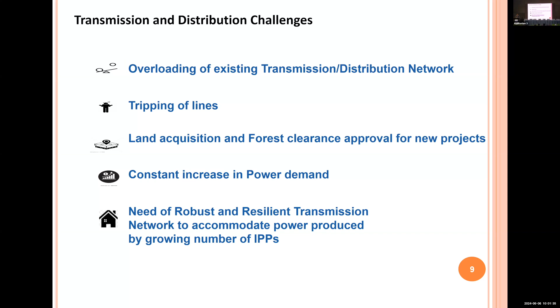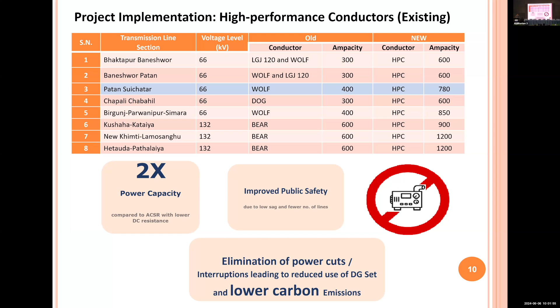So these are some of the projects where we have implemented the high performance conductors, at 66 kV and 132 kV, and the capacity has been doubled. Because of that, it improves public safety, and it eliminates power cuts, leading to reduced use of DG sets and lower carbon emissions. These are the transmission lines where this upgradation work is going on.